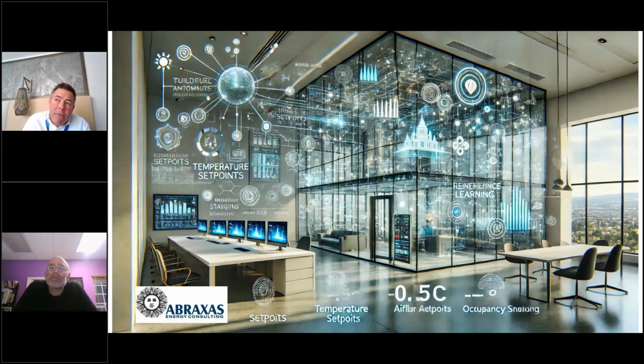We have our air side, our water side, and our engineering limits on all of those subsystems. If AI is going to help us understand those engineering limits, we capture the operating conditions of that equipment at installation. AI is not going to let us deadhead pumps, or overdrive, or attempt to meet flow rates that would cause a chiller to fail or not load up.